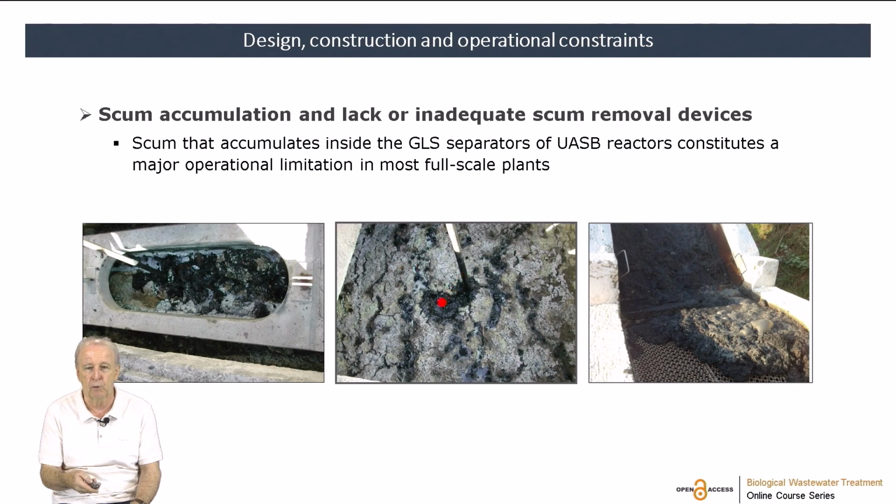So this is an important point. Why is this important? It shows us that this sort of mechanism to remove scum using sucking pipes or pumps is not the ideal one, because when you open these, you have gas release, you have other problems, you have security problems. This is not efficient. There are many problems with this solution for removing scum. Here is another view of one scum that was removed via a device that I'm going to show you in the next slides.